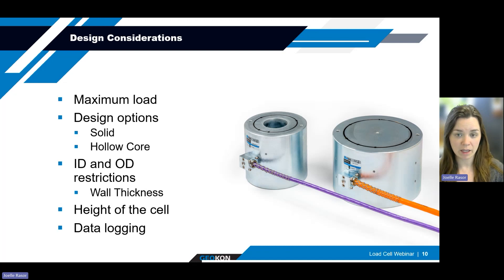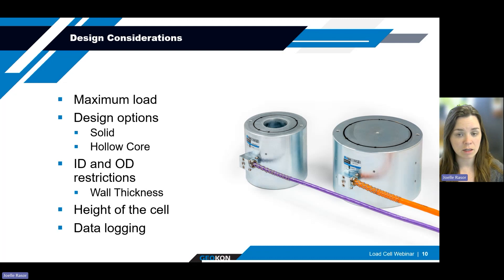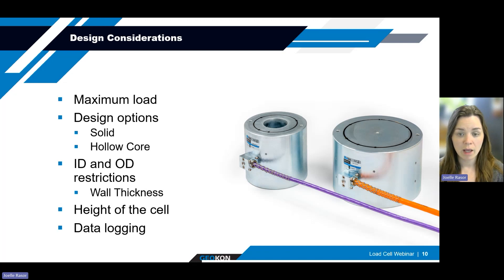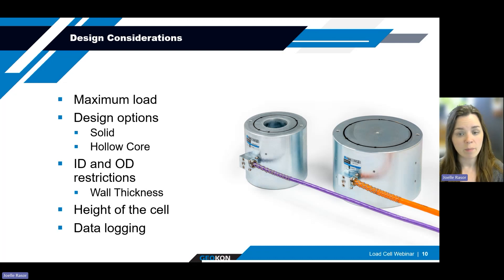It's much more problematic if the center hole is too small. Hollow core load cells can be used in the same applications as solid body load cells, and in some cases adding a center hole can increase the outer diameter of the load cell to better fit an application that needs to meet a particular large outer diameter. Keep in mind that the wall of the load cell body needs to maintain a certain thickness according to the load required. In some cases, overly large ID requirements with small load capacities may not be compatible with this style of load cell.